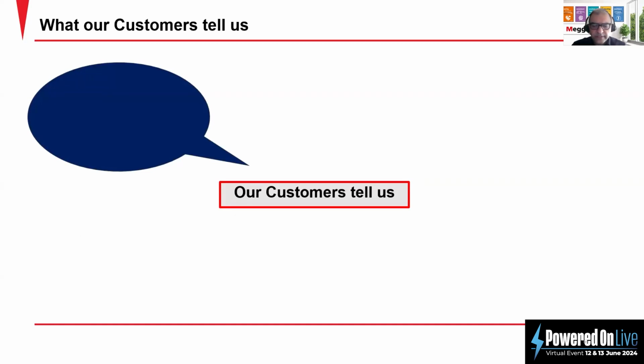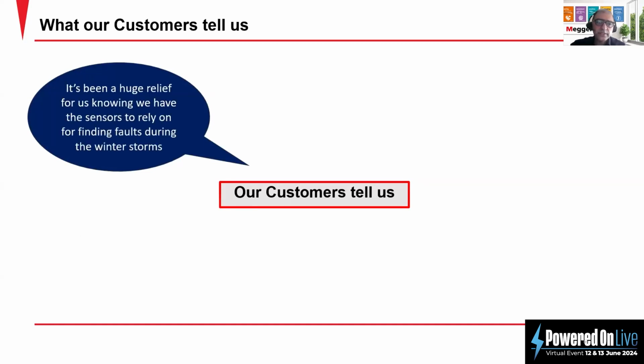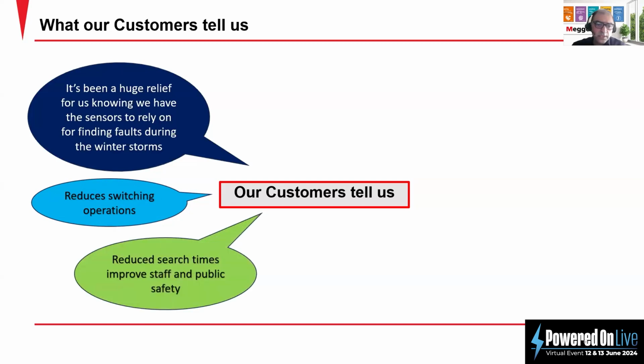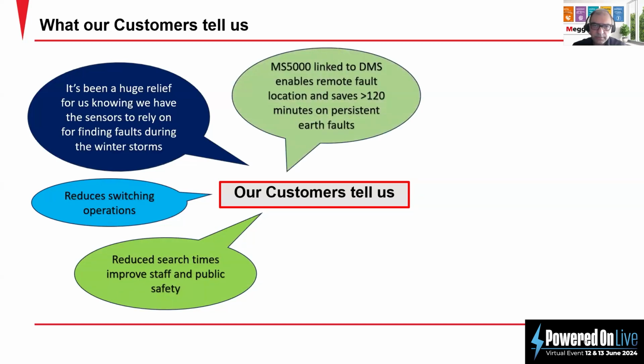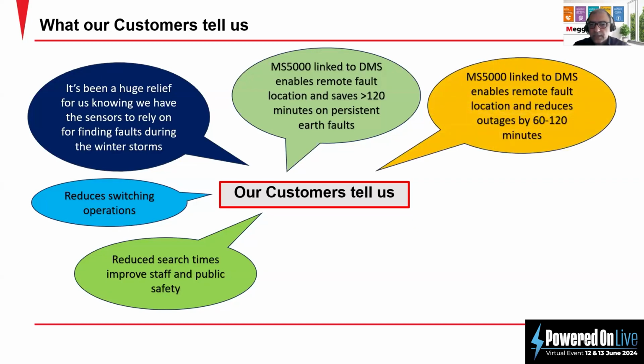Here is some feedback that we are receiving from our customers. Like I said, it's been a huge relief for us knowing we have the sensors to rely on for finding faults during the winter. Other customers mention reducing switching operations, like connecting renewable sources to the network, reducing search time, and improving staff and public safety. MS5000 linked to the DMS enables remote fault location and saves more than 120 minutes on persistent earth faults.